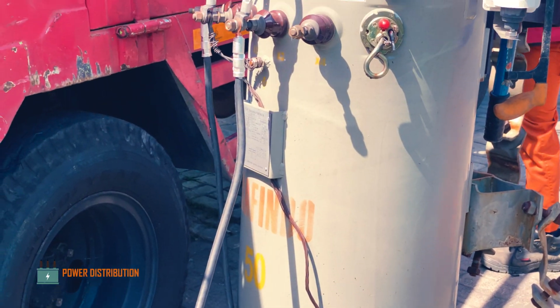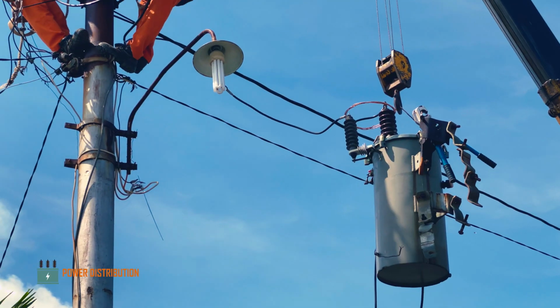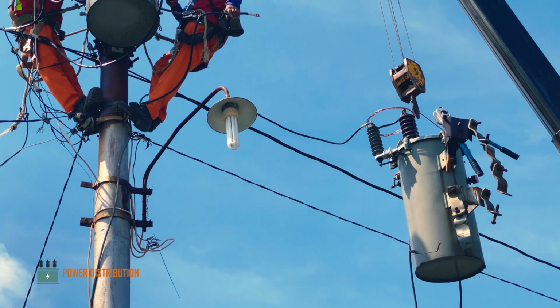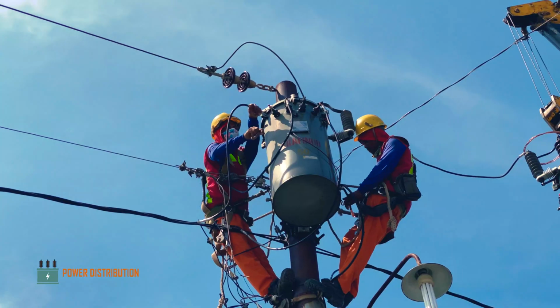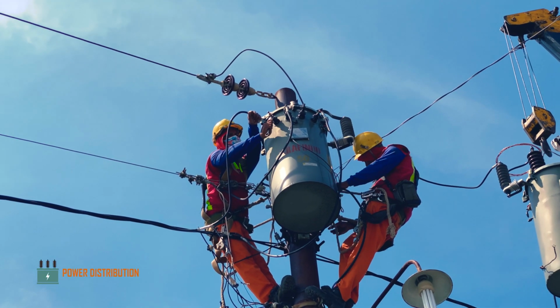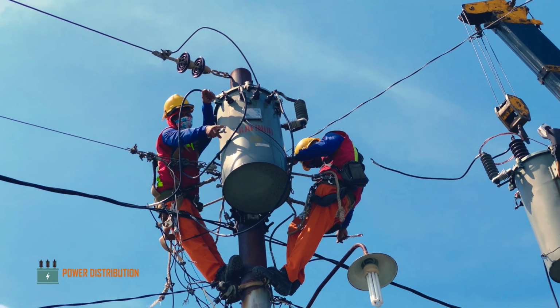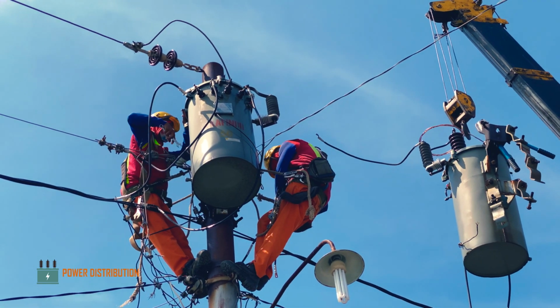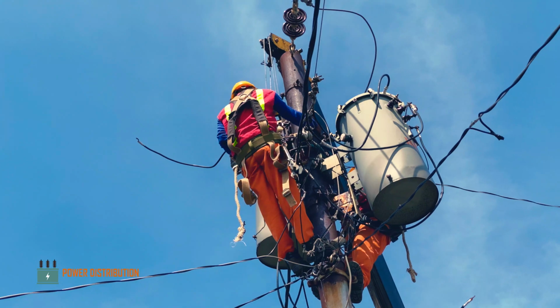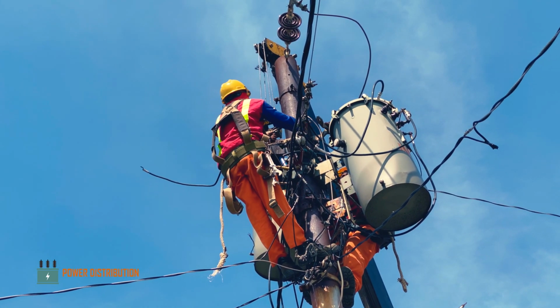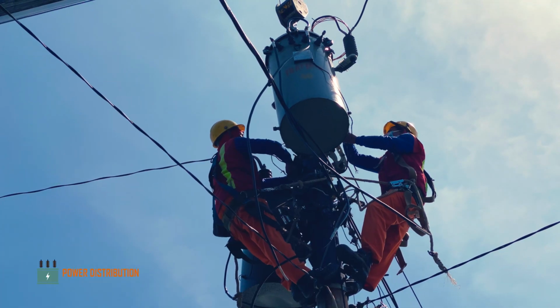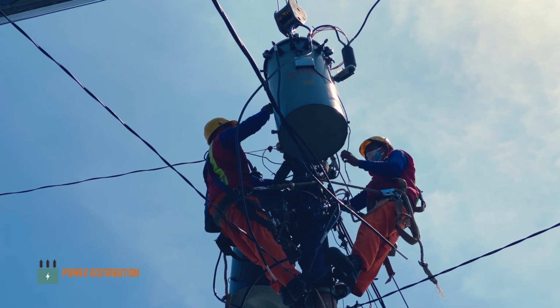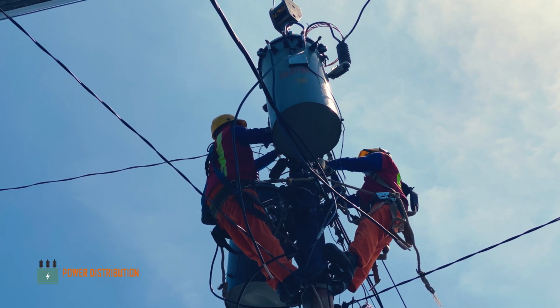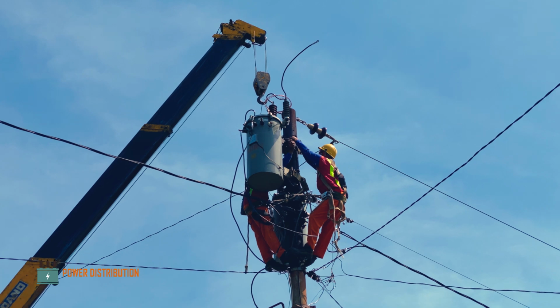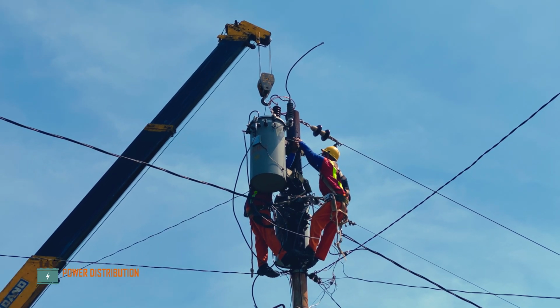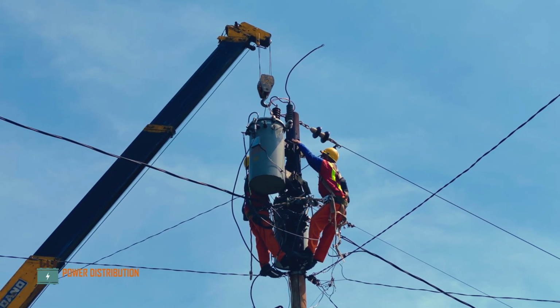Now the new transformer is being lifted up and transferred to the pole after the lineman finished preparing the existing connection. This transformer weighs around 800 pounds or 400 kilos. The lineman receives the transformer and begins to install and secure it onto the pole by fastening the two brackets which hold the transformer onto the pole.